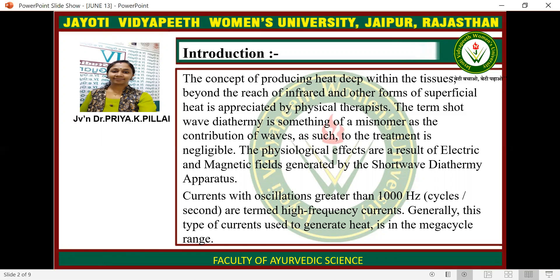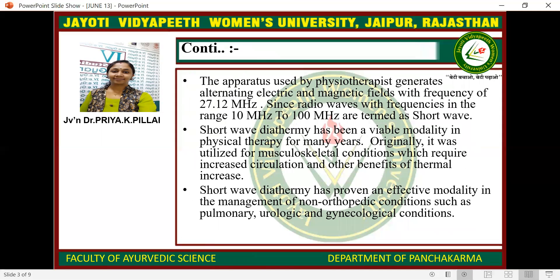Currents with oscillations greater than 1000 Hz are termed high frequency currents. Generally, this type of current used to generate heat is in the megacycle range. The apparatus used by the physiotherapist generates alternating electric and magnetic fields with a frequency of 27.12 MHz. Since radio waves with frequency in the range of 10 MHz to 100 MHz are termed as short wave.